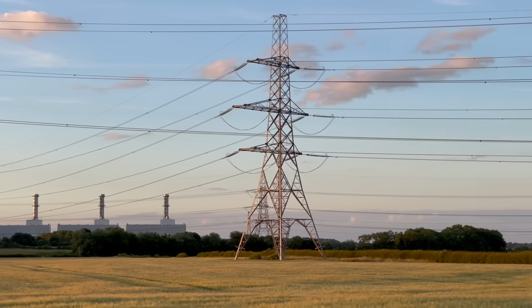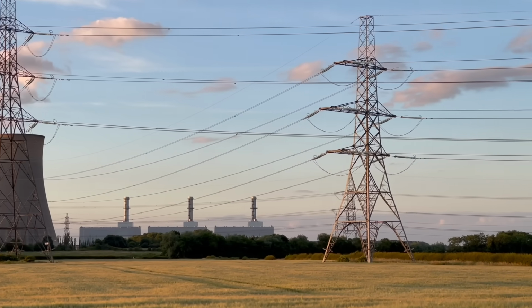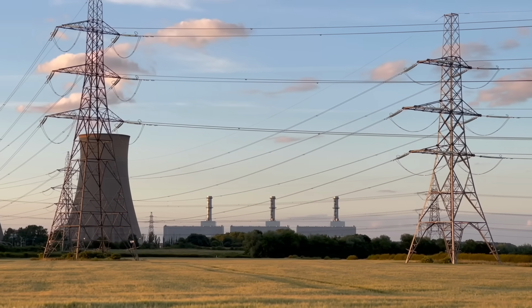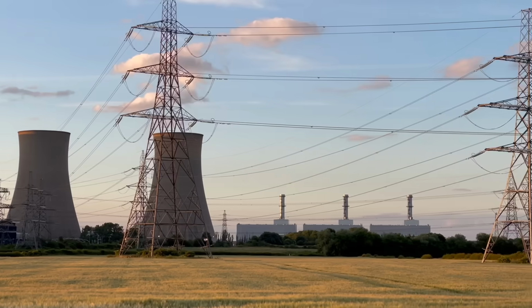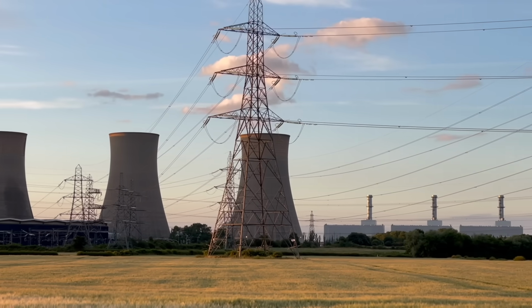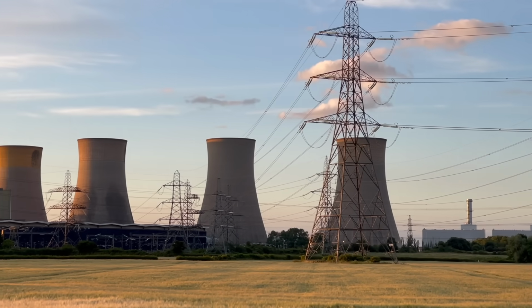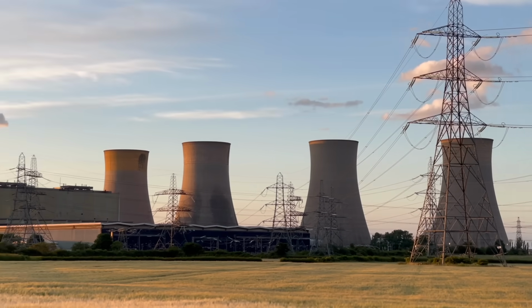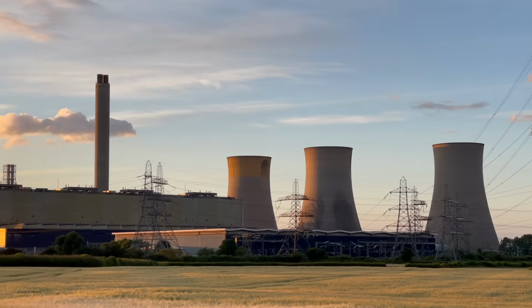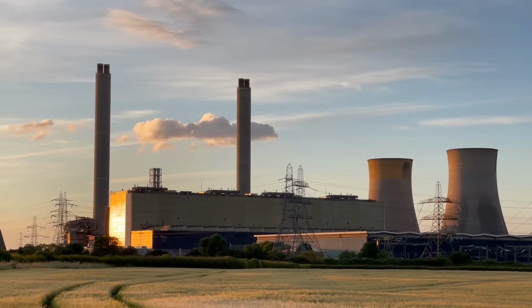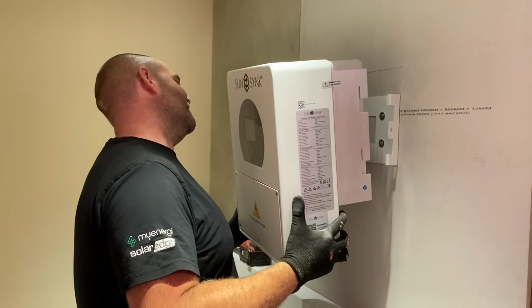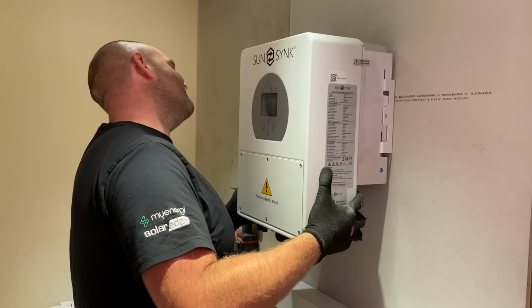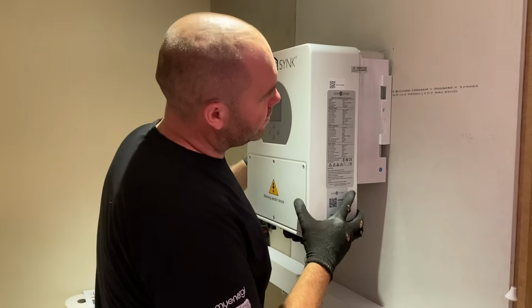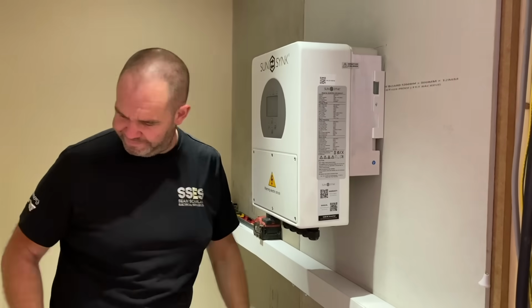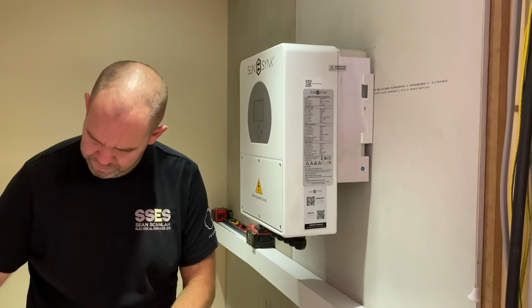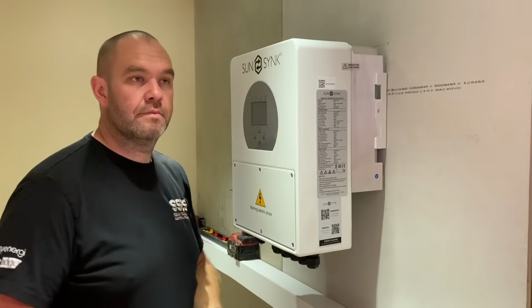The UK's electricity network chiefs are proposing a controversial change to the nation's voltage limits. It's a move they say will make it easier to manage the grid as more renewable energy sources are added. Under the proposal, the lower legal limit of mains voltage would be reduced to 207 volts, bringing the UK in line with European standards. The issue arises because solar inverters can push up local voltages when exporting power to the grid. DNOs currently operate the network with voltage at the top end of its legal limits, where there's little headroom to cope with the rise.